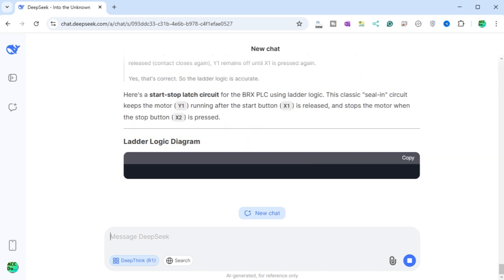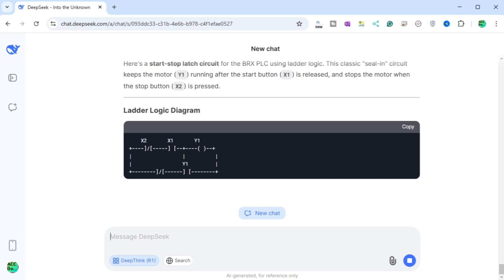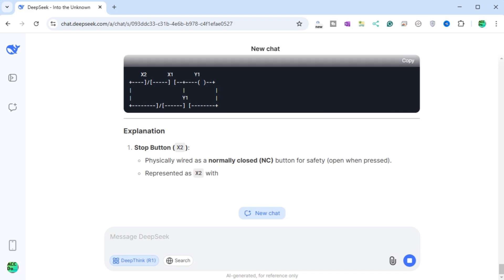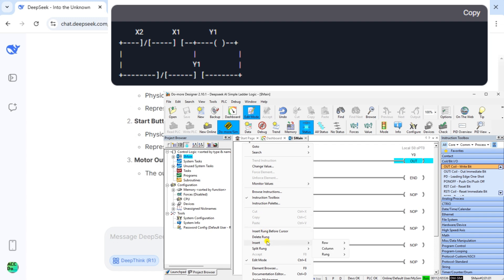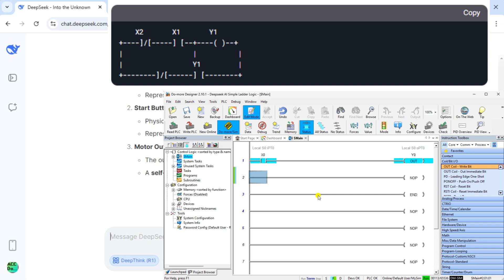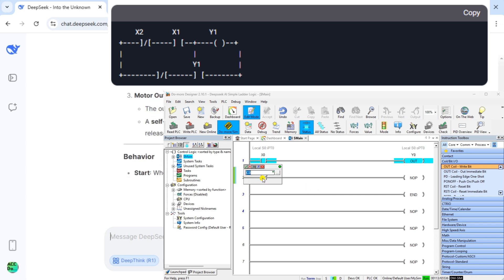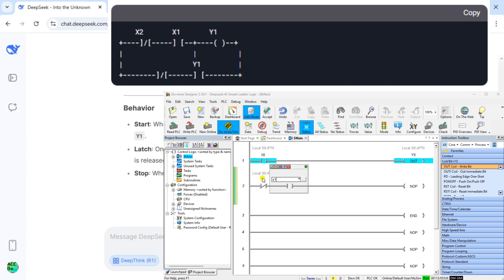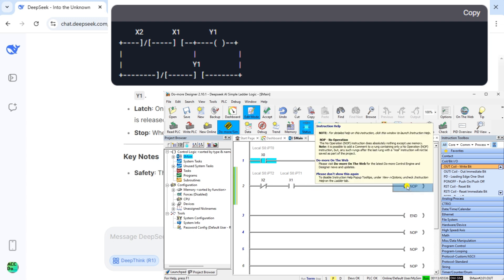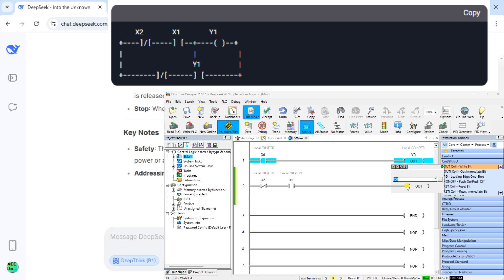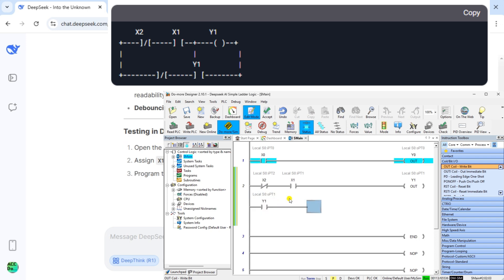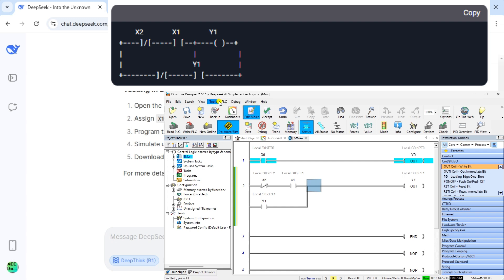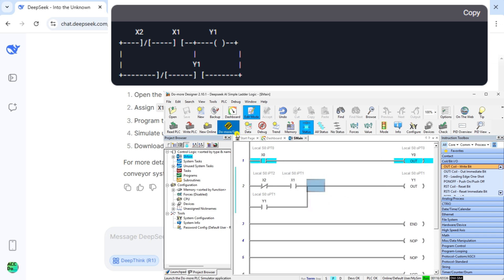Here's the start-stop latch circuit for the BRX PLC using ladder logic. This classic seal-in circuit keeps the motor Y1 running after the start button X1 is released, and stops the motor when the stop button X2 is pressed. Stop button X2: physically wired as normally closed (NC) for safety — open when pressed, represented as a normally closed contact in the ladder. Start button X1: physically wired as normally open (NO) — closed when pressed. Motor output Y1: the output coil Y1 is energized when the circuit is closed. A self-sealing latching contact Y1 in parallel with X1 keeps Y1 energized after X1 is released.